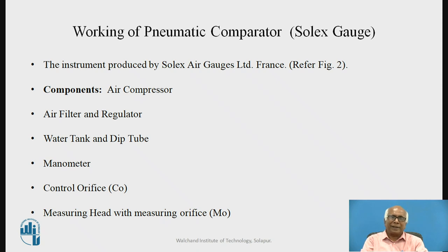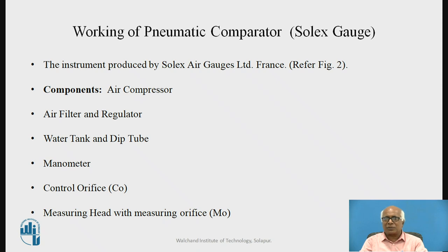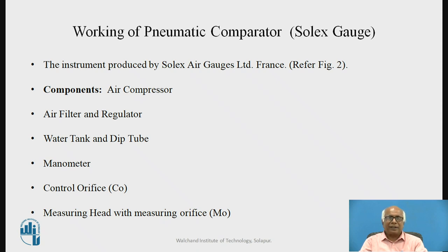The working pneumatic comparator is also commercially known as the Solex gauge or Solex pneumatic gauge. The instrument was first developed and produced by Solex Air Gauge Limited, France. The components of this Solex gauge are: air compressor, air filter and regulator unit, water tank and dip tube, manometer, control orifice, and measuring head with measuring orifice.